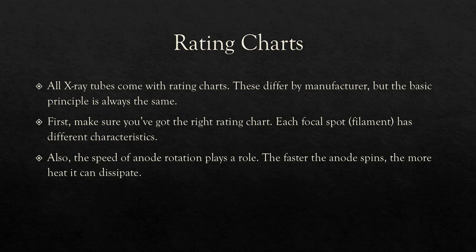Every X-ray tube comes with a tube rating chart. These things differ by manufacturer, but the basic premise is always the same. You look at your tube rating chart — it's going to have some lines and curves, and you just plot on the chart where your technique lies. If it's below the curve, you're good. If you're above the curve, chances are you're not going to be able to make that exposure. Every tube has at least one rating chart because there's a separate chart for small filament and large filament. The faster your anode can spin, the more heat your tube can tolerate, so you'll have to look at the chart for your correct focal spot size and anode rotation.